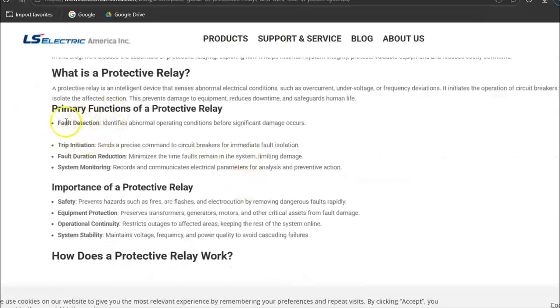They have basically 4 stages. Fault detection. They identify abnormal operating conditions instantly before significant damage occurs. This is done by connecting it to CTs and PTs and measures voltage, measures current. Trip initiation sends a precise command to trip circuit breakers for fault isolation. Fault duration reduction, so it minimizes the time the fault is there. And also the newer ones are system monitoring. They can record and analyze and send data off to central areas.